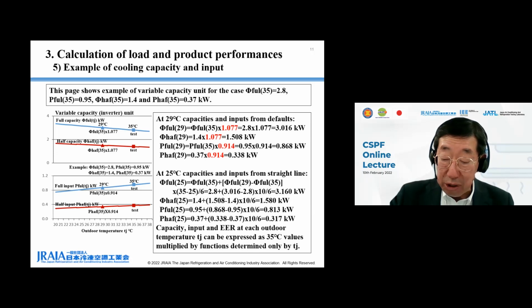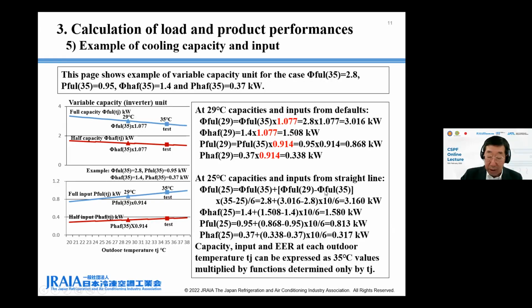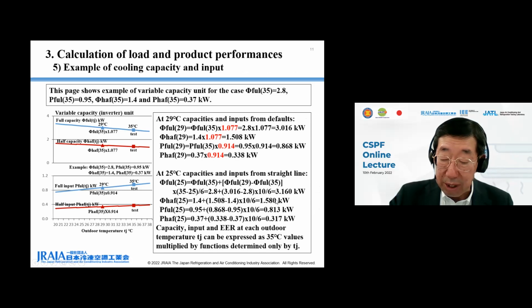At outdoor temperature 25 degrees C, the equation of the straight line connecting 35 and 29 degrees C is expressed as shown. Using this equation, 25 degrees C full capacity becomes 3.160 kilowatt. In the same way, 25 degrees C half capacity becomes 1.580 kilowatt. 25 degrees C full input becomes 0.813 kilowatt, and 25 degrees C half input becomes 0.317 kilowatt.